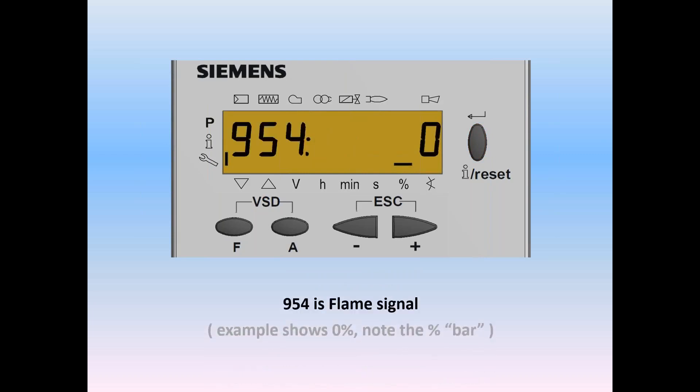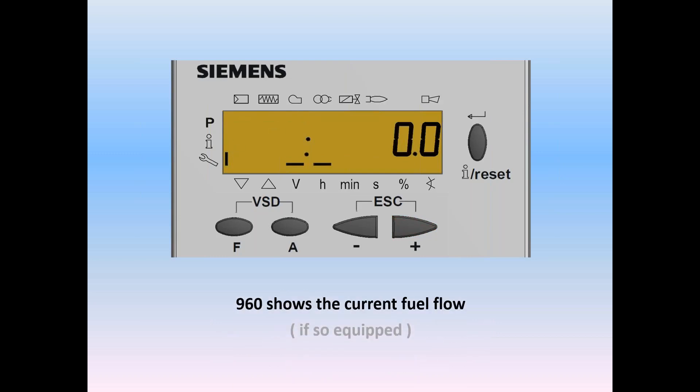First thing you'll see on your screen is 954 flashing. You'll notice that on the left, the little wrench has a bar indicating that we're at the service level. The parameter is 954, and the value is zero. And you'll notice that there's a bar above the percent sign, which is telling us that we're getting a zero percent flame signal. That's because the burner shut down. If you push the plus key, we can move it on. And now we get parameter 960. 960 shows us the current fuel flow. In this case, it's zero.